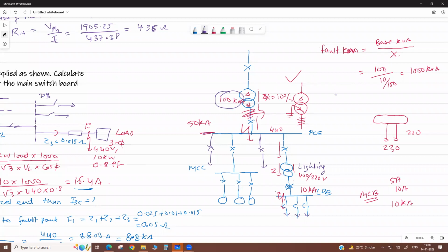Then we calculate the short circuit fault current, that is fault kVA divided by √3 into line voltage. The voltage is, if we calculate an HT side fault or LV side fault, we take here what is the HV side voltage and what is the LT side voltage. Okay, correct. But here it is a simple one.